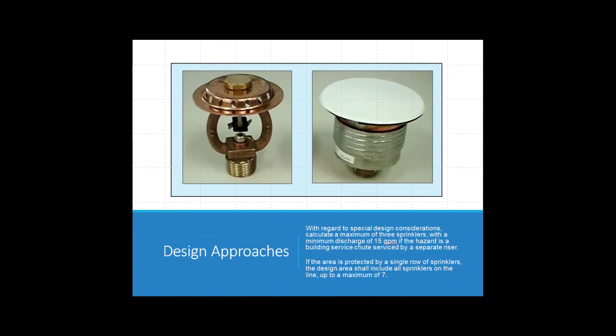You can calculate a maximum of 3 sprinklers with a minimum discharge of 15 gallons per minute if the hazard is a building service chute serviced by a separate riser.